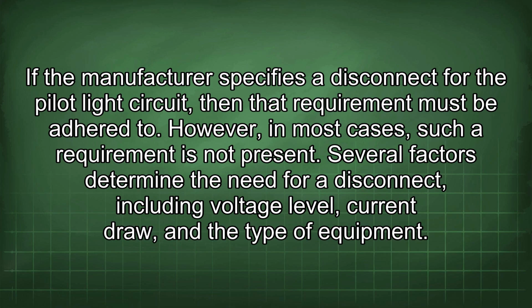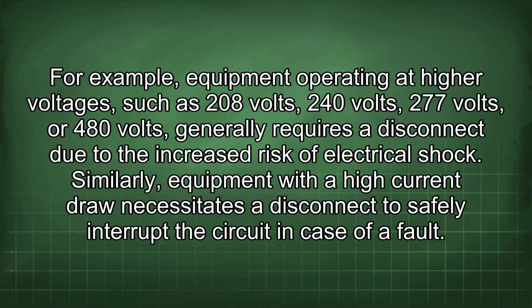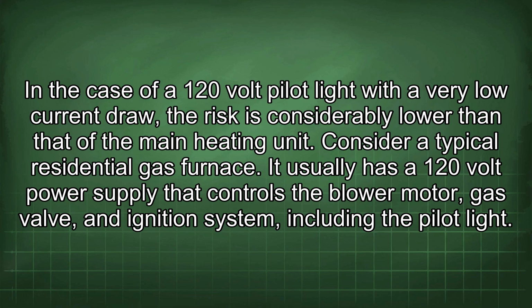Several factors determine the need for a disconnect, including voltage level, current draw, and the type of equipment. For example, equipment operating at higher voltages, such as 208 volts, 240 volts, 277 volts, or 480 volts, generally requires a disconnect due to the increased risk of electrical shock. Similarly, equipment with a high current draw necessitates a disconnect to safely interrupt the circuit in case of a fault. In the case of a 120-volt pilot light with a very low current draw, the risk is considerably lower than that of the main heating unit.